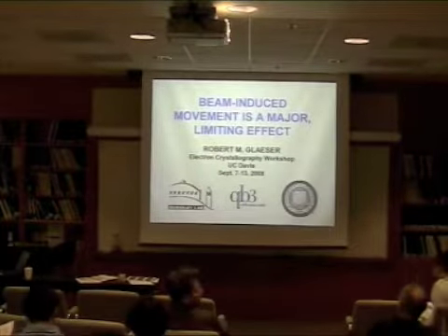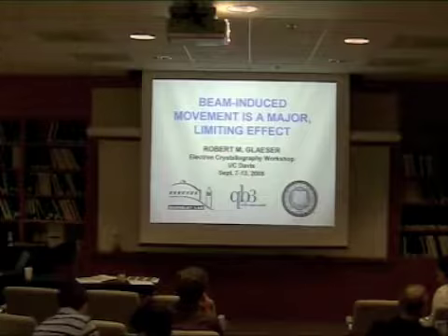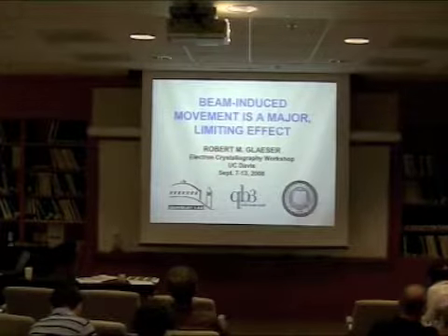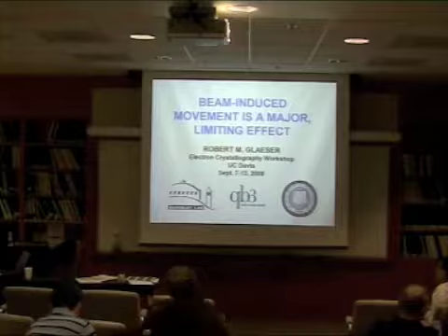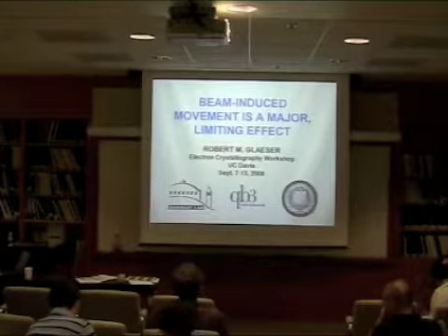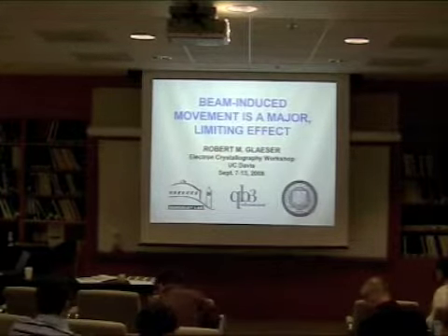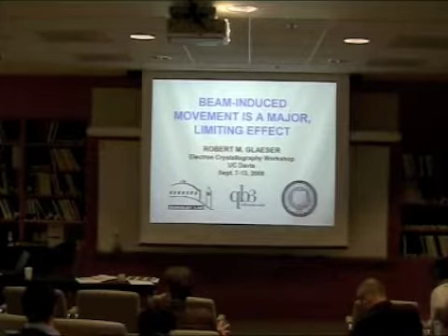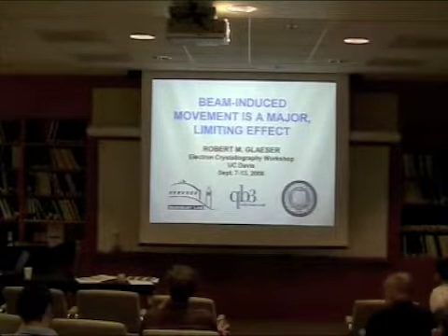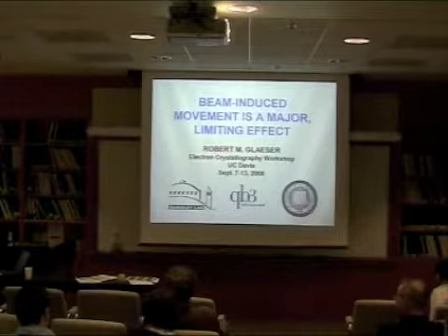Beam-induced movement results in three effects I'm concerned about. One is degraded resolution in an untilted specimen — you don't get the signal or resolution that you often expect. The second is loss of resolution in the direction perpendicular to the tilt axis in tilted specimens, above and beyond what happens with untilted specimens. The third, which the field suffers a lot from, is movement of particles in samples used for cryo-electron tomography, where images in a dataset are not consistent with one another because things have moved around.